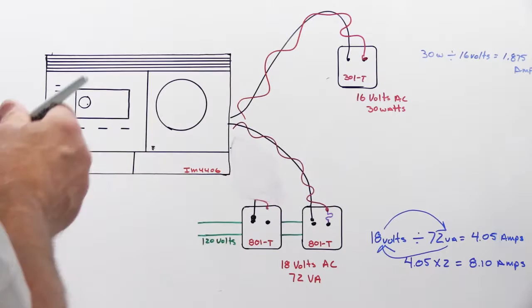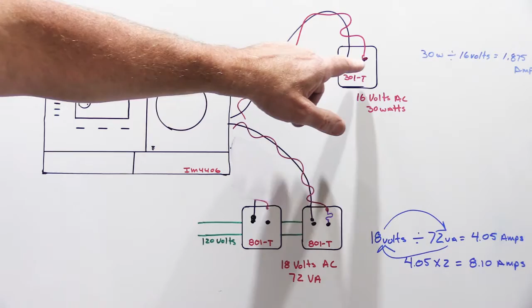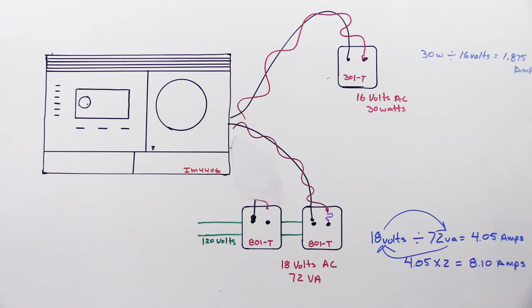So we'll run one wire to one, and we'll run the other wire in the pair to the other one, and we'll connect, and we'll turn on the circuit breaker. And what we're going to do is measure the voltage here. So a free running 301T will have very slightly more than 16 volts AC, because transformers are usually rated under their normal or nominal load, which means when you have a device connected to it that's using an appropriate amount of current from the transformer.